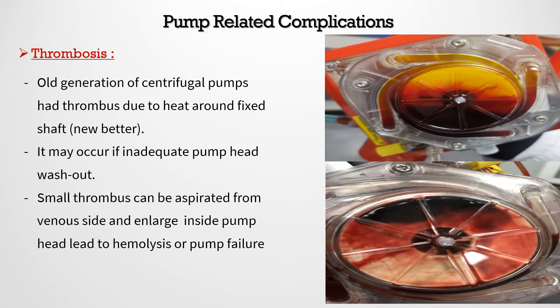The third pump-related complication is thrombosis. Centrifugal pump head thrombus is due to heat around the fixed shaft. It may also occur with inadequate pump head washout, allowing blood to retain inside the pump head. Small thrombi can be aspirated by the pump from the venous side; larger ones accumulate inside the pump head. Both can lead to hemolysis or pump failure. These two pictures show different pump thrombosis cases from my unit — one presented with complete pump failure, the other with hemolysis in the circuit.